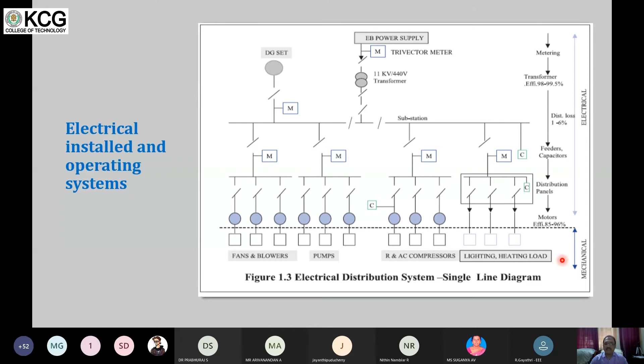Like I said, I have 1 or 2 slides on each of the products. Transformer is the heart of the plant. Any distribution transformer, the optimum loading is approximately 50% to 60%, because the peak efficiency of a transformer happens around 30 to 35%. Oil-cooled transformers, the peak efficiency is between 30 to 35% only. But then to size a transformer for 1/3 of your requirement is criminal. Therefore, I suggest 50 to 60% is the best loading factor for a transformer.